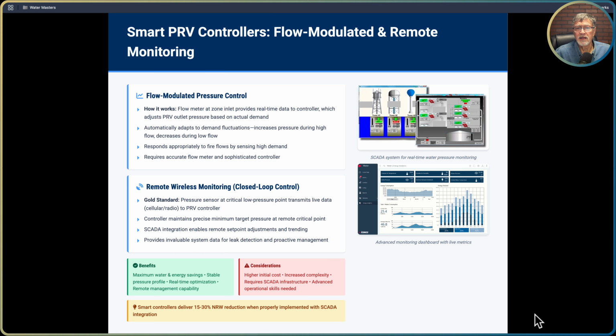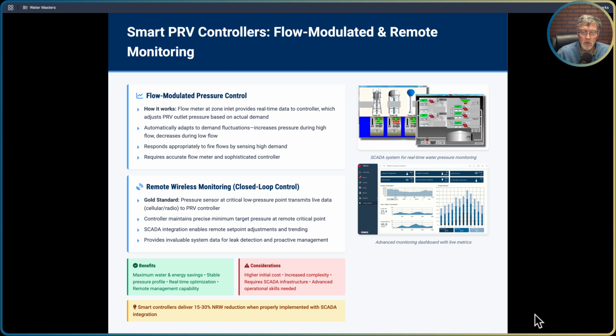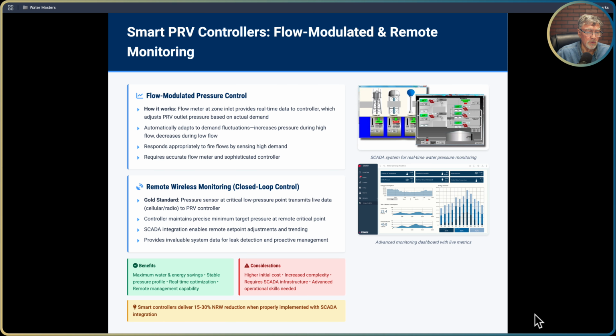So you're looking at where you're getting high and low pressures in your system, and you're monitoring those and adjusting the rest of the pressure to suit that. SCADA integration enables remote set point adjustments and trends, and it provides invaluable system data for leak detection and proactive management. So that's really your gold standard. You're going to get maximum water and energy savings, stable pressure profile, real-time optimization, and remote management capability.